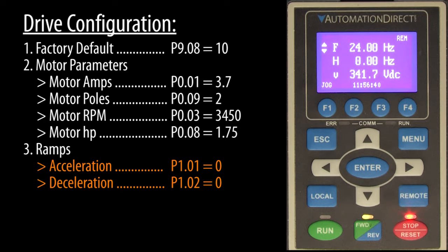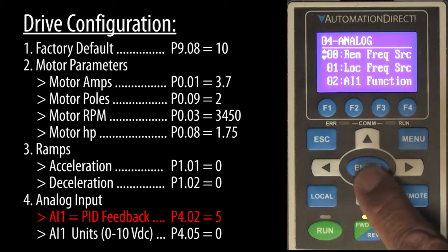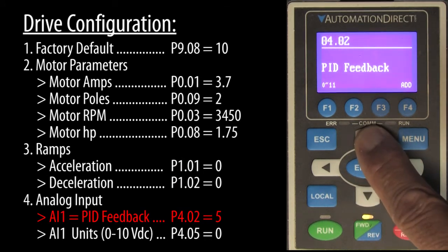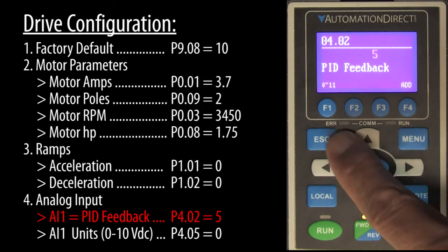I also zeroed out the acceleration and deceleration ramps because they will interfere with the PID function. We need to tell the drive that we are using analog input 1 as the PID feedback signal and that it will be used as a 0 to 10 volt signal.